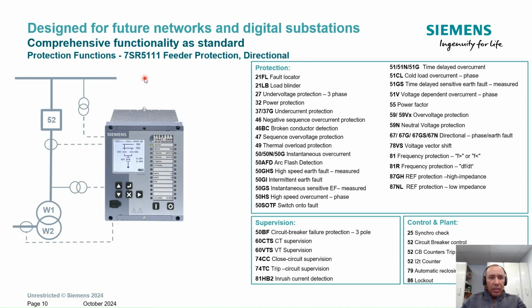The second option would be the 7SR5111. This device is still a feeder device, but this device brings you a VT input. That means that this device is a directional relay. These are other protection functions that you can perform using CT, VT, and power protection. Okay, special mention for renewables now: reverse power, also frequency protection, and also vector shift. That's very common for renewables.